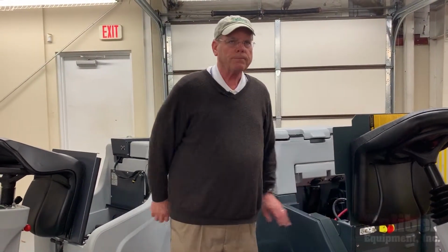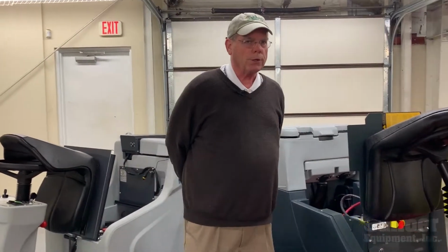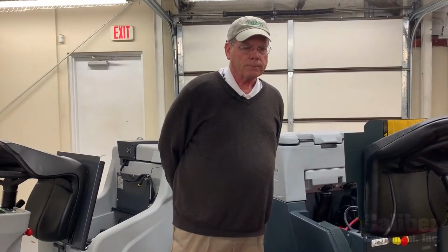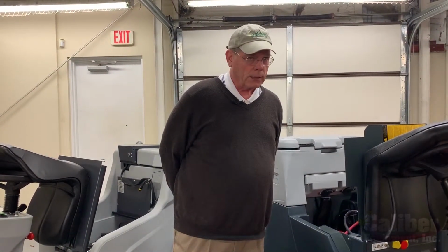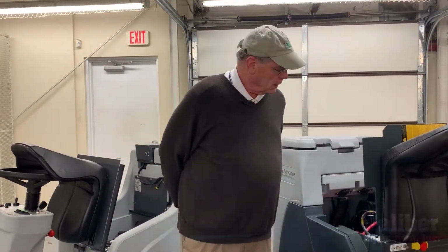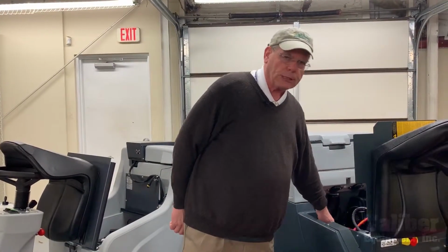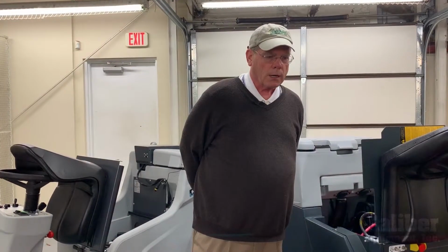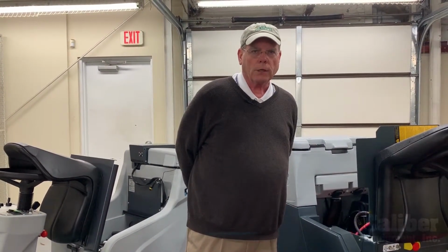Batteries have generally a manufacturer's warranty of 1 year. And batteries can fail. They can be bad right from the manufacturer. So if you're not getting enough runtime on your machine, one of the things you need to check is whether you have electrolyte in the cells. And there's also ways of checking the status of the battery. Each one of these caps indicates a 2-volt cell.